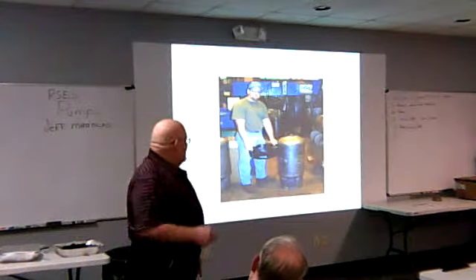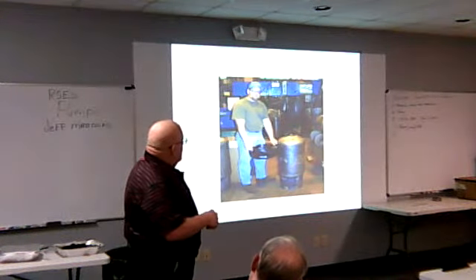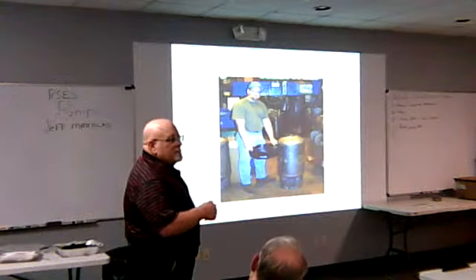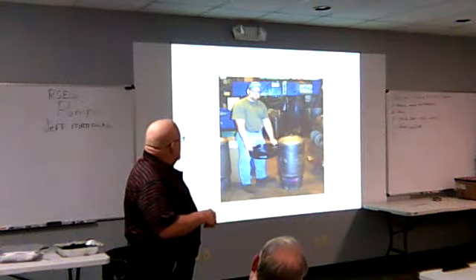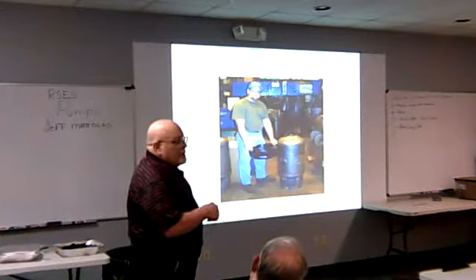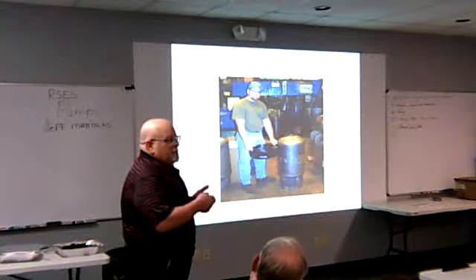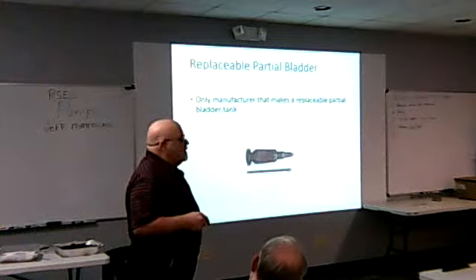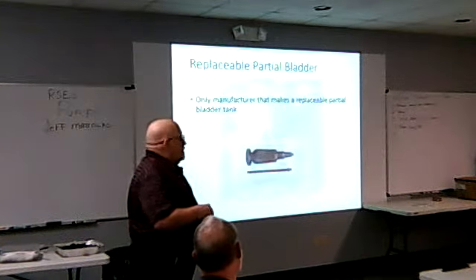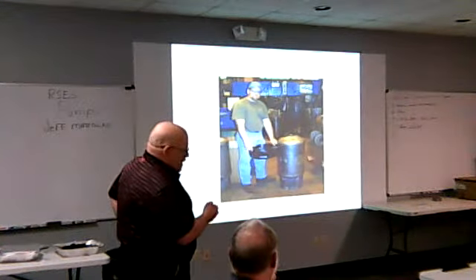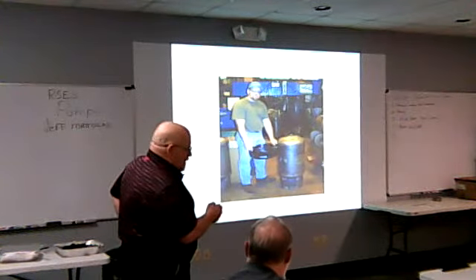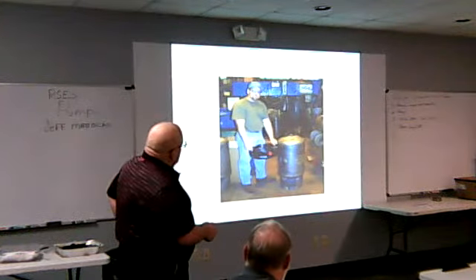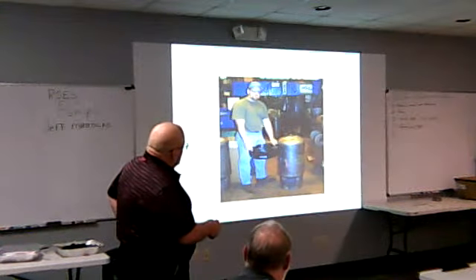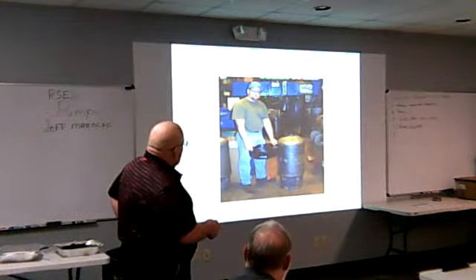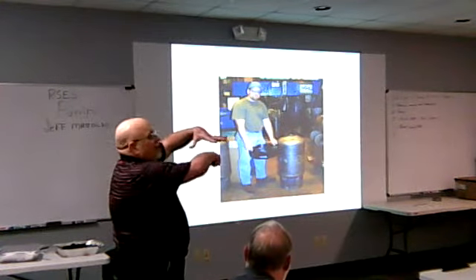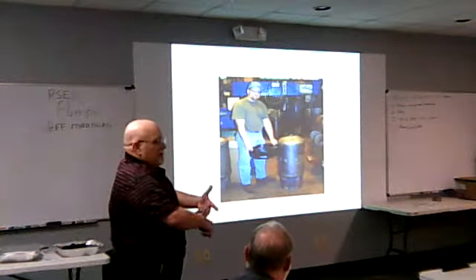But this bladder just goes up and down. Water's on the top, air's on the bottom, or vice versa. Well, it's the other way. No, the connection's at the bottom. So water's down here, air's up here. It's like your rib cage bladder. So the air pressure is on top of the bladder, and the water comes up from the bottom. It has like a dip tube. So when the air is charged in here, it's going to expand down. And as the water comes in, it's going to compress that bladder, compress the air. And it's going to work just like when you're breathing, your lungs.